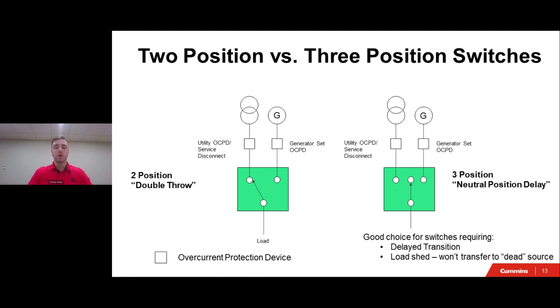We will discuss this a little later on in the presentation, but this type of transfer switch is great for any open delayed transitions for emergency applications. This three position switch can also allow for load shedding because the neutral position that is once again in that center ensures that you will not transfer to a dead source. So just to briefly describe the main differences, on the left there is that two position switch. You just have the ability to transfer from the emergency to normal, whereas in the three position switch off to the right there, you have the normal and then the center off and then the emergency source. So switching to that center off position allows for open delayed transitions for emergency applications, as well as allows for the ability to load shed.